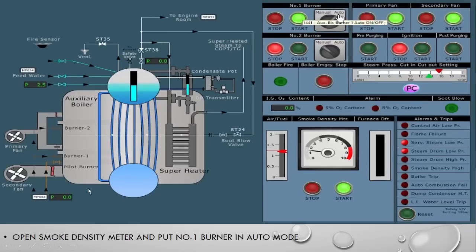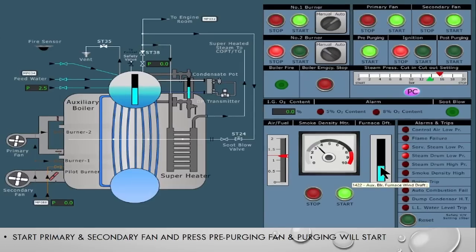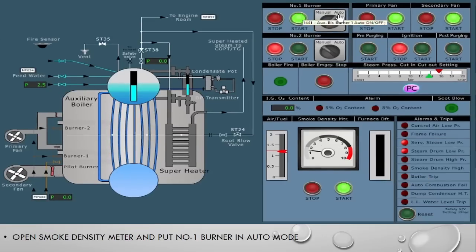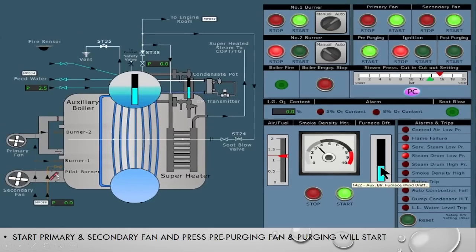Now we will start the boiler. First we open the smoke density meter and put number one burner in auto. We are firing number one burner only, as most ships have only one burner and one pilot burner. After starting the smoke density meter and putting number one burner in auto, the primary fan and secondary fan will start. As the fans start, the boiler begins pre-purging. You can see the draft fan valve is almost 60 percent open and slowly increasing — more air is being sent inside the boiler.